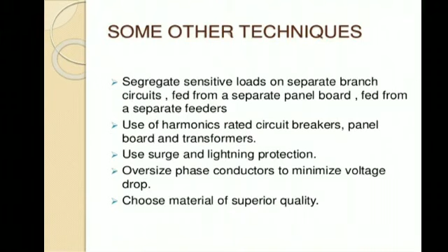And some other techniques include the use of surge and lightning protection, segregating sensitive loads on a separate branch circuit fed from a separate panel board fed from separate feeders, use of harmonic rated circuit breakers, panel boards and transformers, oversized phase conductors to minimize voltage drop, and choosing materials of superior quality.